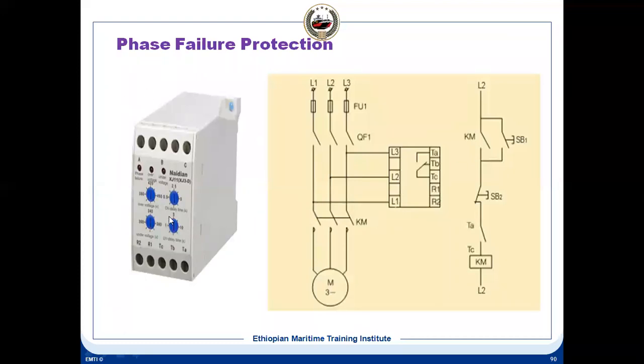This is the relay, it looks like this. You have three connections here, L1, L2, L3, and here you have only one control connection, that is TA, connected here. So whenever any one phase fails, this will open and open the main contactor, it will trip.